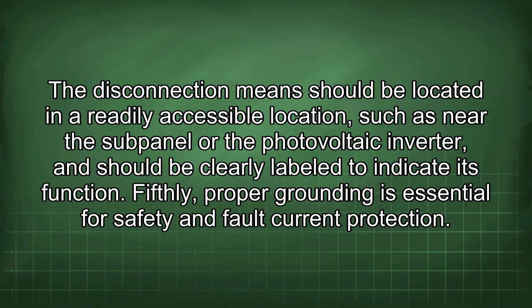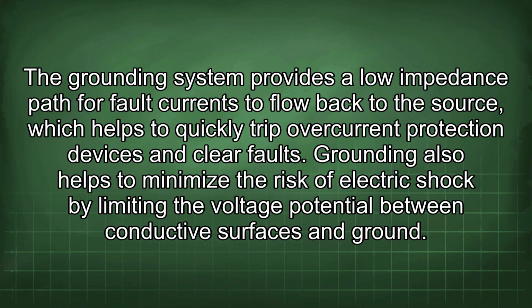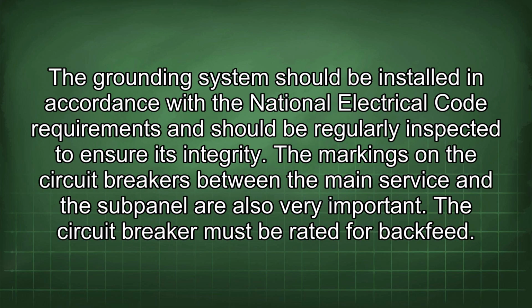Fifthly, proper grounding is essential for safety and fault current protection. The grounding system provides a low impedance path for fault currents to flow back to the source, which helps to quickly trip overcurrent protection devices and clear faults. Grounding also helps to minimize the risk of electric shock by limiting the voltage potential between conductive surfaces and ground.